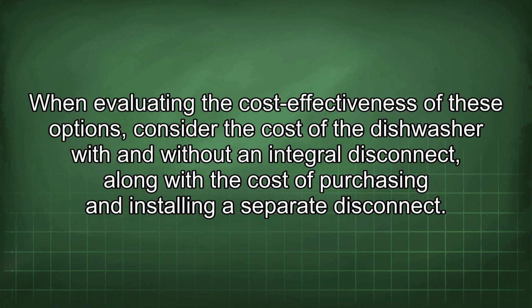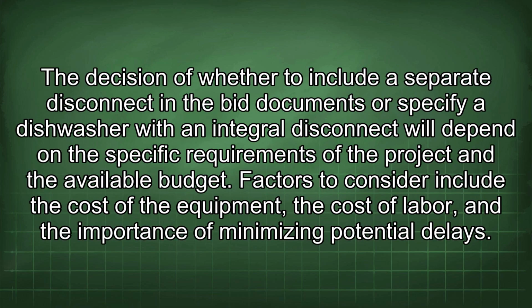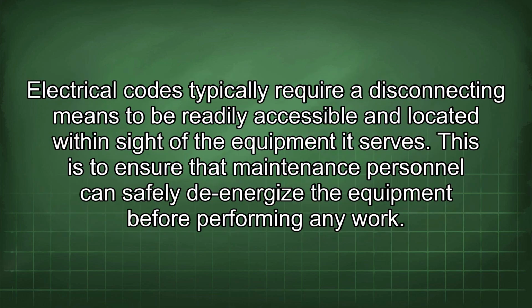When evaluating the cost effectiveness of these options, consider the cost of the dishwasher with and without an integral disconnect, along with the cost of purchasing and installing a separate disconnect. The decision of whether to include a separate disconnect in the bid documents or specify a dishwasher with an integral disconnect will depend on the specific requirements of the project and the available budget. Factors to consider include the cost of the equipment, the cost of labor, and the importance of minimizing potential delays. Electrical codes typically require a disconnecting means to be readily accessible and located within sight of the equipment it serves. This is to ensure that maintenance personnel can safely de-energize the equipment before performing any work.